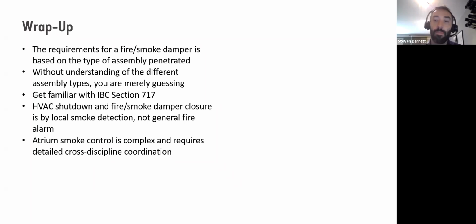And remember the local detection typically for HVAC shutdown and fire or smoke damper is by the local and associated smoke detector, not the general alarm. And then if you do work on an atrium project, it's complex, and be sure to coordinate with all the other disciplines throughout design and all the way through construction, because it is a very complicated design.